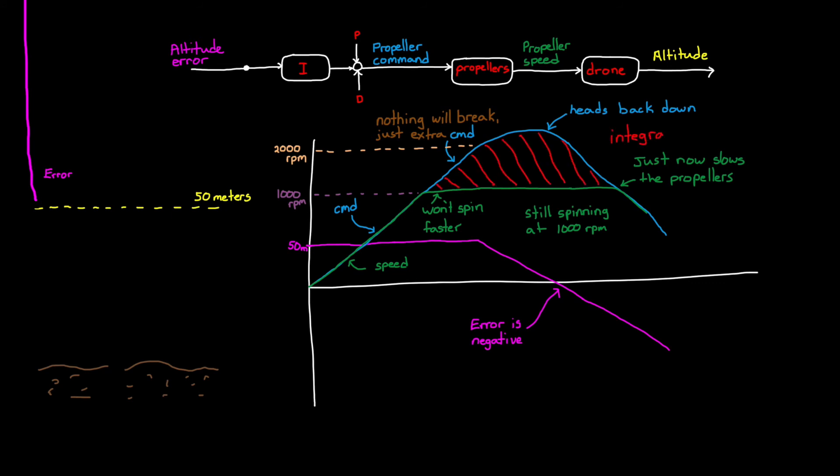This is called integral windup, and it's something we need to protect against in our PID controller, because you never know if you're going to get into a situation where an actuator saturates. And when something does saturate, we want to minimize the time it takes to reverse the command when the error changes signs. So we need to implement some kind of anti-windup method.